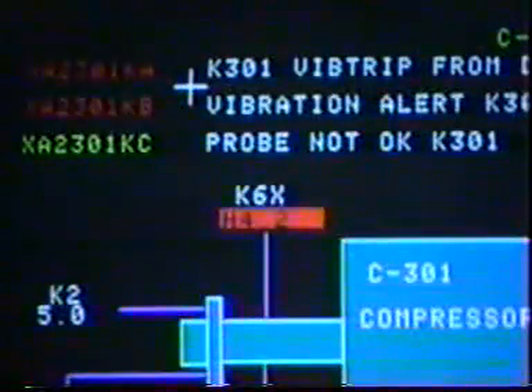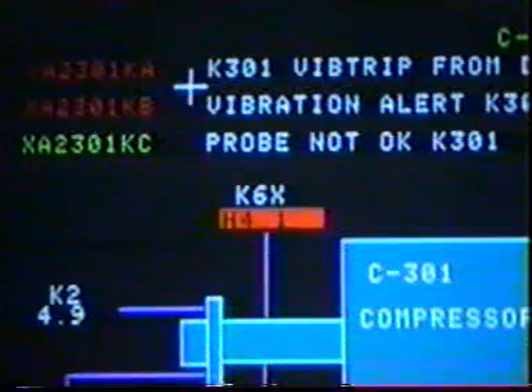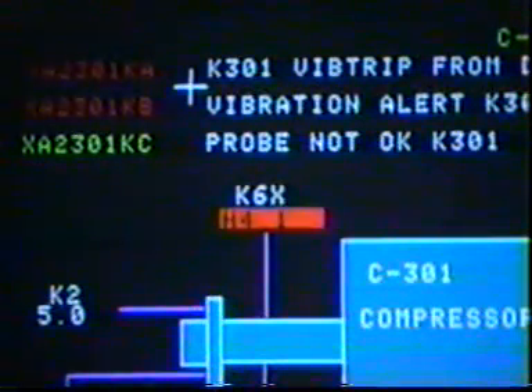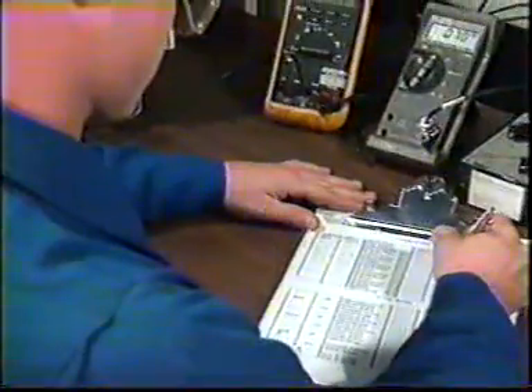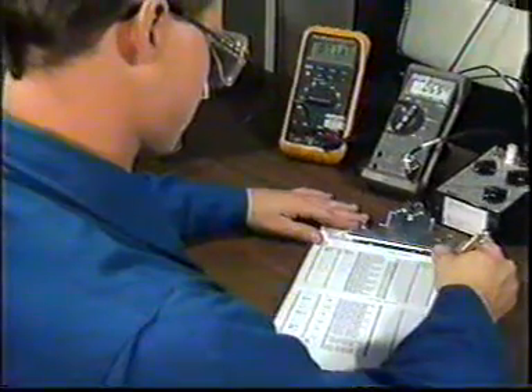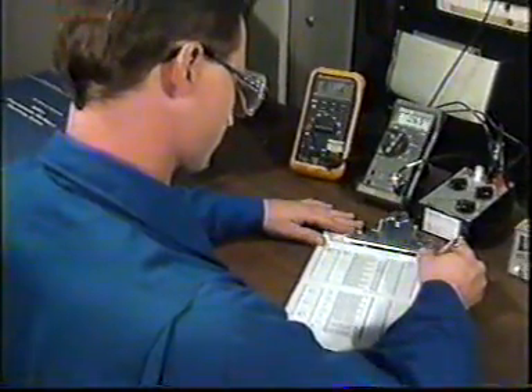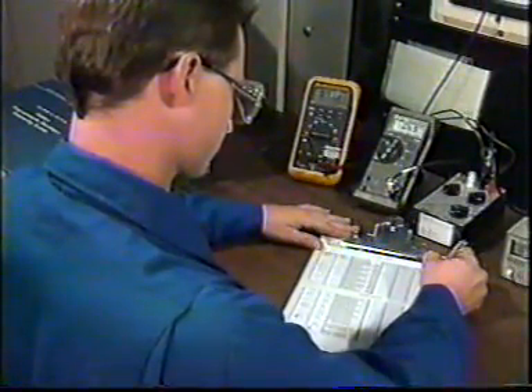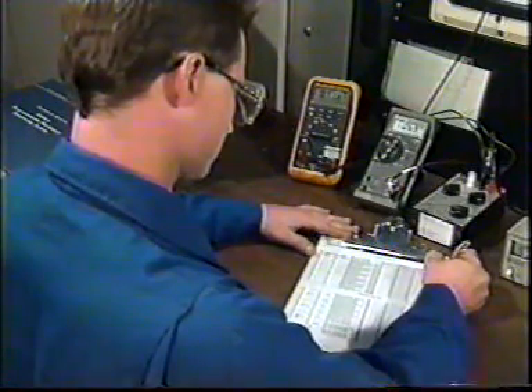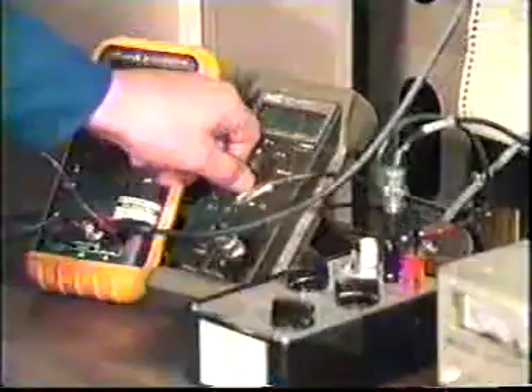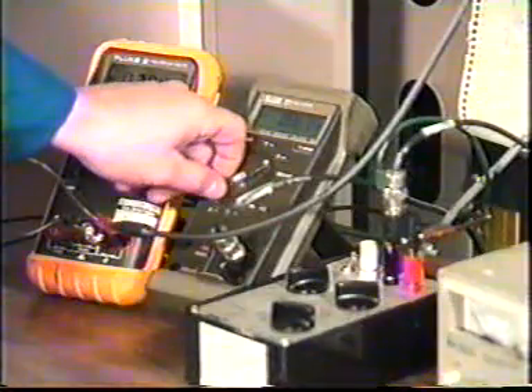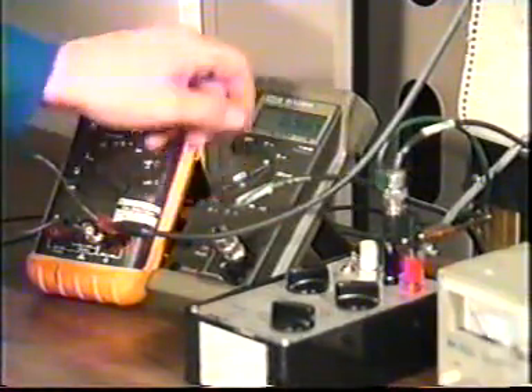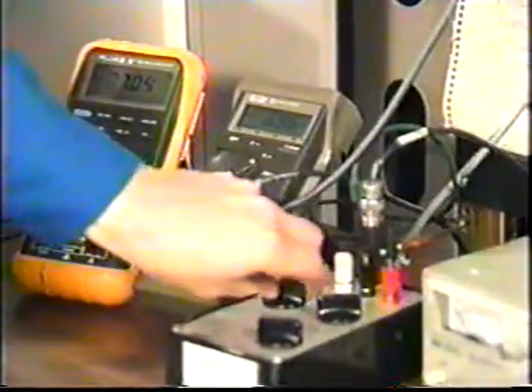In some systems, an alarm or shutdown may be a function of the monitor circuit. If this is the case, be sure to follow your facility and manufacturer's instructions to calibrate the monitor. Analog outputs are typically rated in percentage of full-scale output values. You'll need to calculate acceptable output values for your inputs. It's a good idea to take at least 3 sets of readings to ensure the output values are consistent.